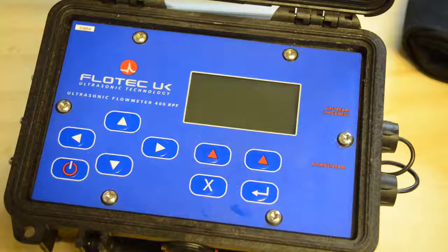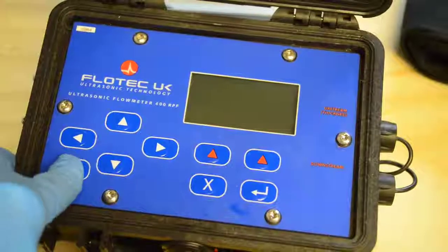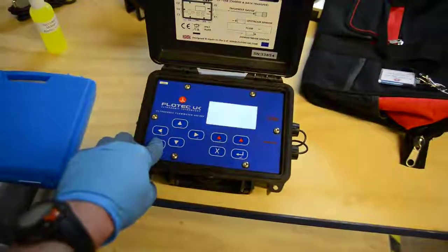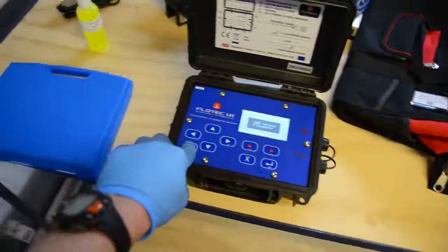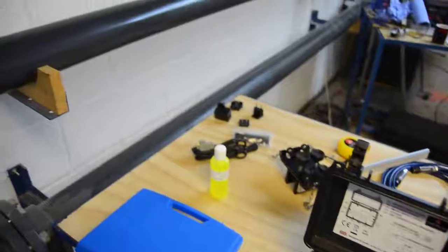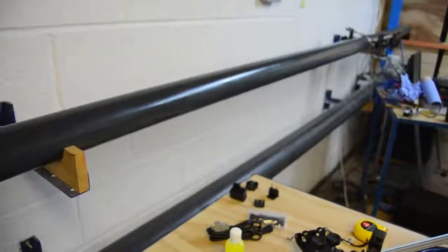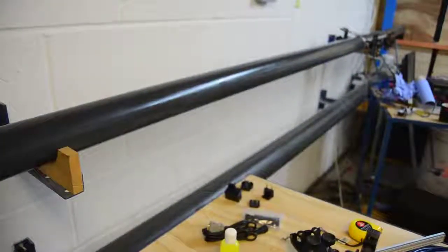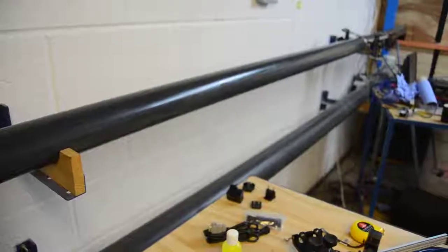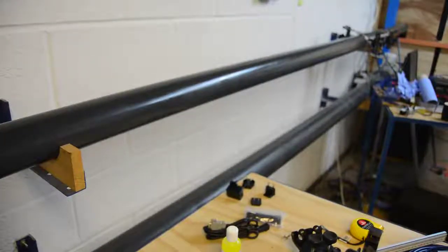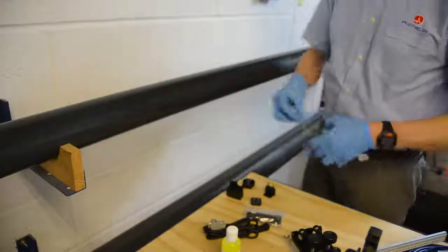Here we have the flow meter and we're in our calibration rig, so if I just power the thing up, and then as you can see we've just got our calibration pipe here. So I'm just going to go through the process of setting it up on the pipe. So let's start by measuring the circumference of the pipe.